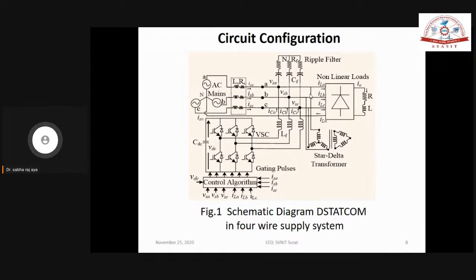Again, we always say we are going to compensate the distortion. But in actual practice, there is one more conclusion. If you look carefully, suppose in supply voltage and current, before compensation, the distortion in voltage may be 4% and in current 21%. Assume that. Without any filter, supply voltage distortion is 4% and current 21%. After connecting this converter, you observe the supply current distortion near 21, maybe 22, 20.5, 20, some value near. The supply voltage distortion is near 4, meaning 3.9, 3.5, 4.5. That depends upon other parameters.